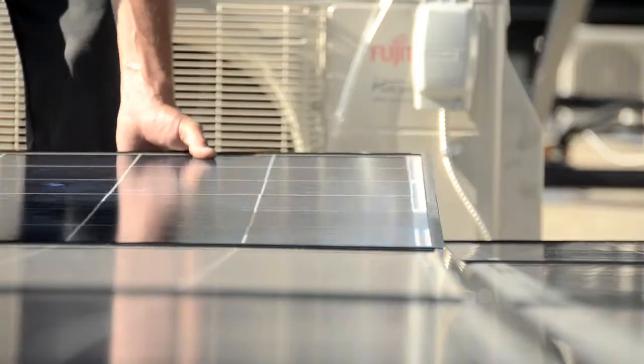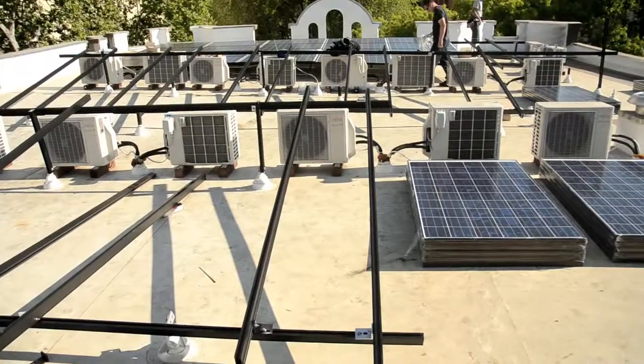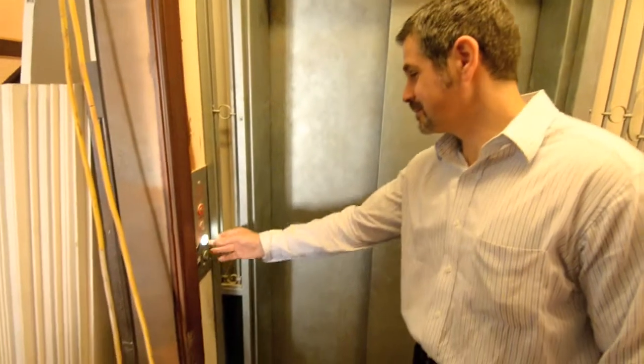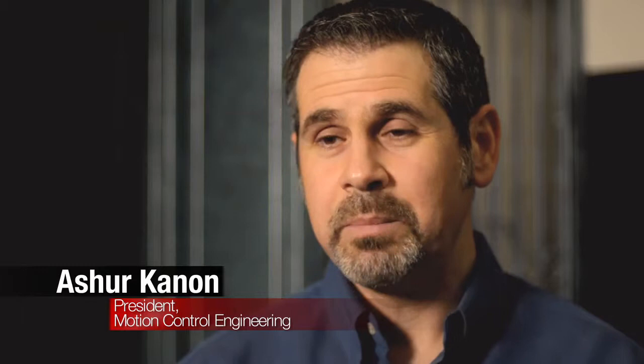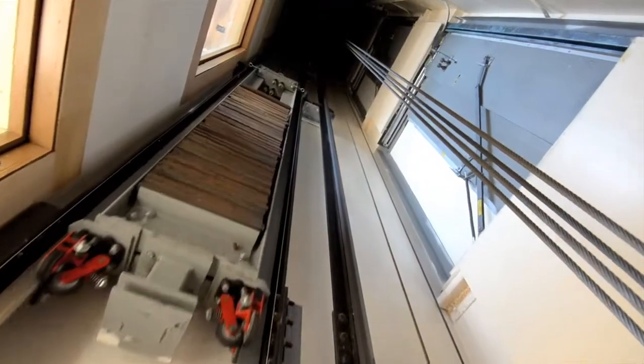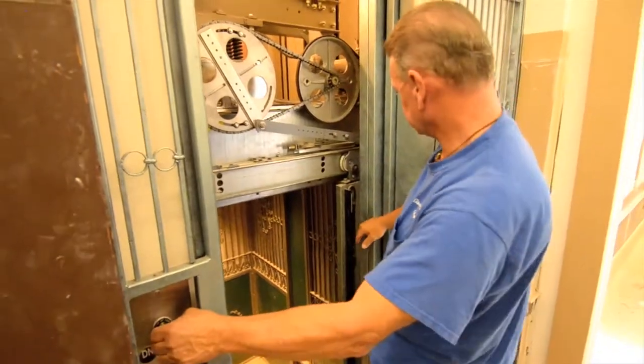That PV system is going to cover the house load — things like corridor lighting, the rec room, heating and air conditioning. The old-style cage elevator was historic but needed to be replaced. We replaced it with a new energy-efficient elevator. The system installed is what's called regenerative, meaning that power flows both ways — it consumes power when doing work and puts power back during overhauling conditions. This system is 90-plus percent efficient, so power consumption is only 8 to 10% of the overall power to operate the elevator.